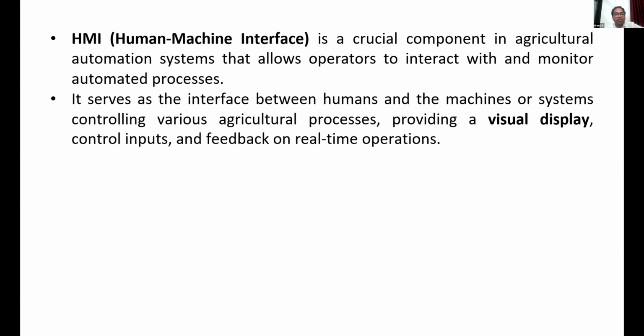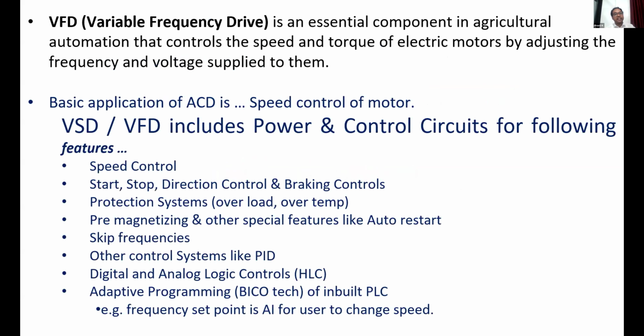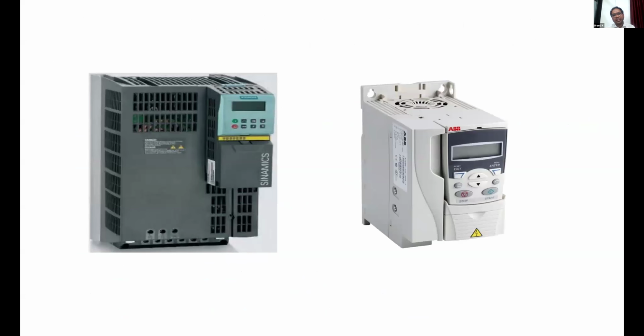So HMI plays a very important role in automation. And the next part is the AC drive. And AC drive is the variable frequency drive. I can say AC VFD plays a very crucial role in automation. The main function of the VFD is to control the speed of the induction motor. Other than that function, we can use it if you don't want to use the starter for start stop purpose, for protection system, pre magnetizing, for skip frequency, you can use the VFD. This is a very simple device which is looking like this.